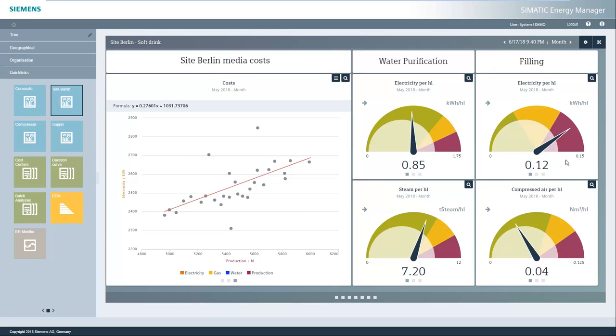In the next section — filling — the consumption of electrical power for each production volume is significantly increased and is located in the red zone. Compressed air consumption, however, is located in the green zone. This means that the consumption of electrical power in the filling section must be optimized.